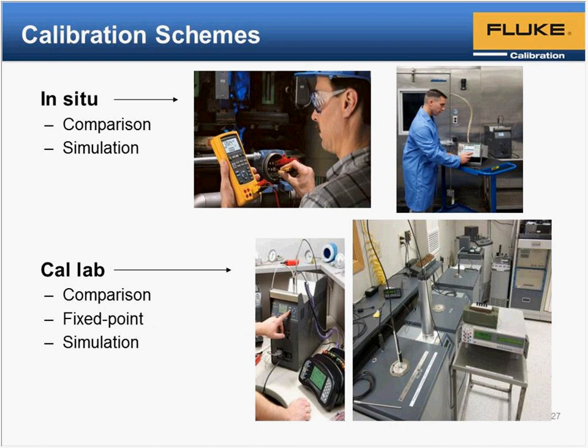A lot of calibrations are done on site or in situ. Typically there is a comparison calibration where the thermocouple is brought out and put into a heat source, like the right-hand picture here, and compared with a reference temperature probe. But oftentimes in a transmitter situation, the thermocouple is simulated. So you connect a thermocouple simulator to the transmitter, and you verify that the transmitter is measuring thermocouple voltage correctly. The assumption is that the thermocouple is working just fine.